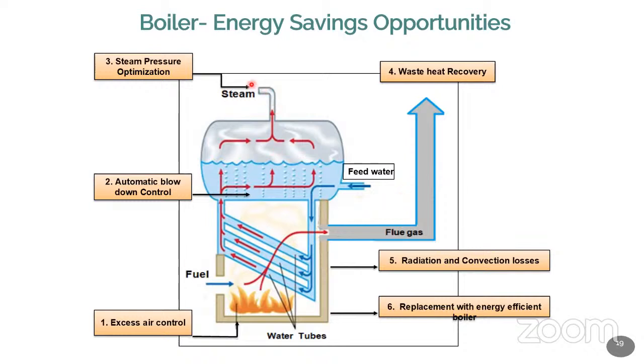Now similarly, optimize the pressure of the steam wherever and whenever required. Only then can you operate the boiler at a very optimal level. Then there is waste heat recovery from the flue gas, and then the convection and radiation losses outside the boiler, outside the heat chamber. So these are all the areas where we can work on the reduction of losses.